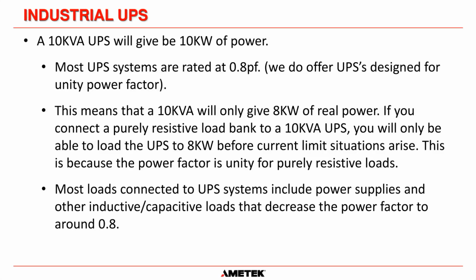The next misconception is a 10 kVA UPS will give you 10 kilowatts of power. Once again, that's not correct. Most UPS systems, industrial UPS systems, are rated at 0.8 power factor. Now, AMETEK does offer UPS designs that are unity power factor, but the standard offering that we have is 0.8 power factor. That means a 10 kVA UPS will only give you 8 kilowatts of real power.